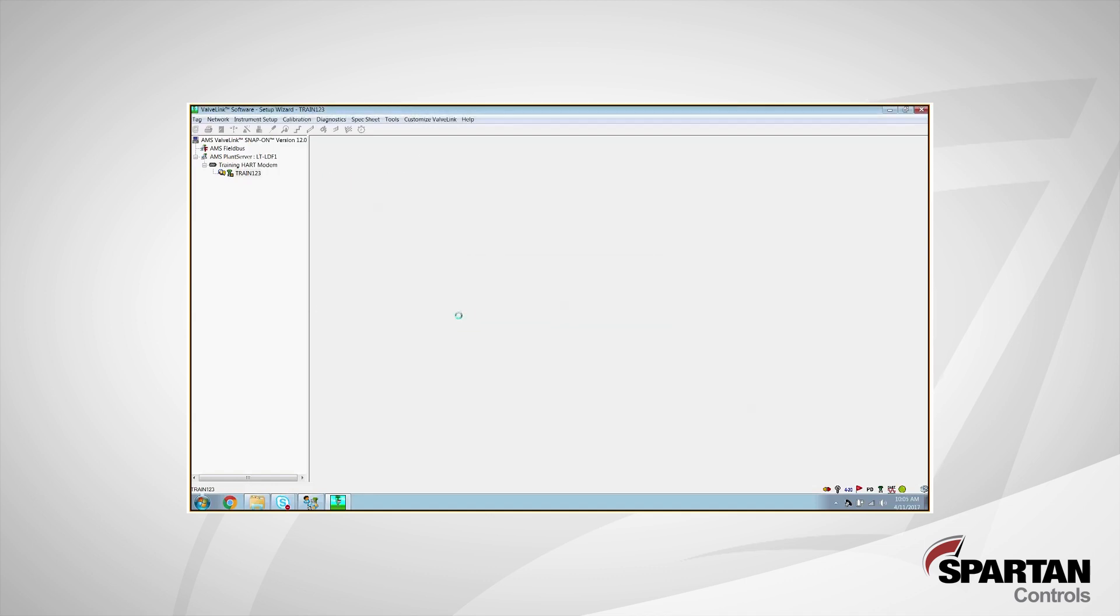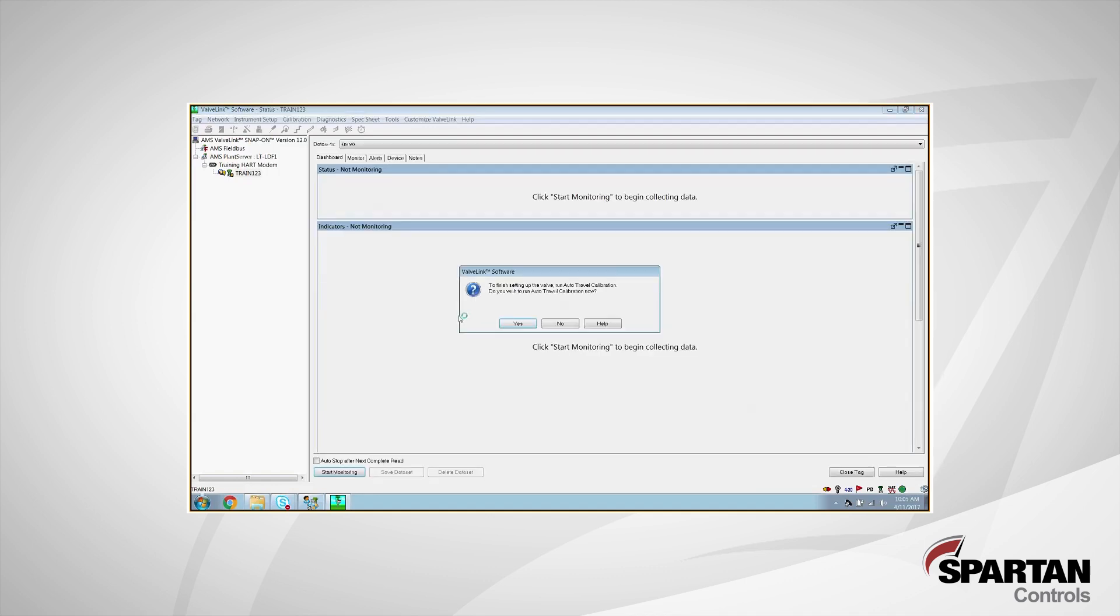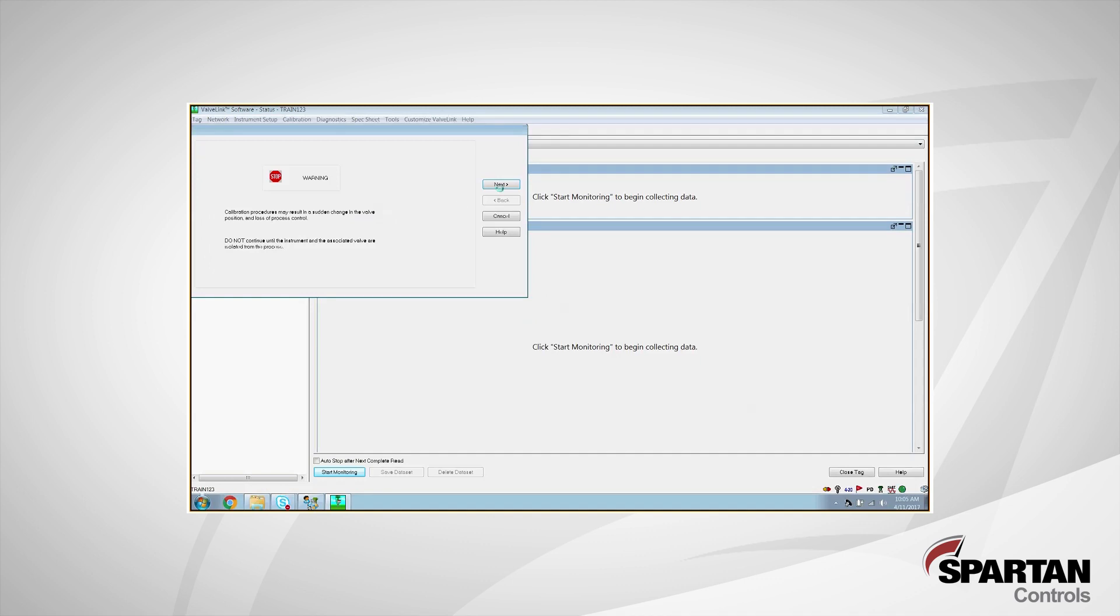Next, it's going to ask us whether we want to run the auto travel calibration. In most cases, you'll choose yes. There are a few exceptions where you would say no. Those exceptions would be if you have a low powered and low CV solenoid tubed in between your DVC and your actuator. If you have an extremely large actuator that needs a large volume of air, or if you're working on a system that doesn't have hard stops. An example of that would be like a louver system. You'd want to say no and do a manual travel calibration. But since our system has two hard stops, I'm going to choose yes. And then we're going to click next and it's going to start to move our valve and set our zero and our span on our assembly here.